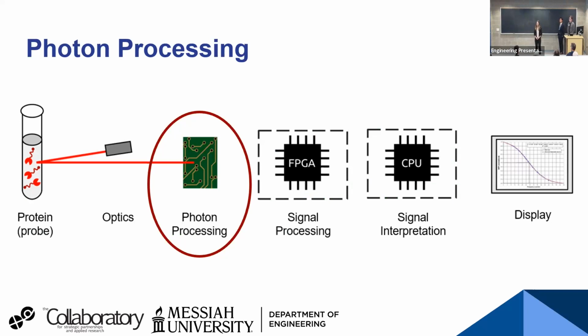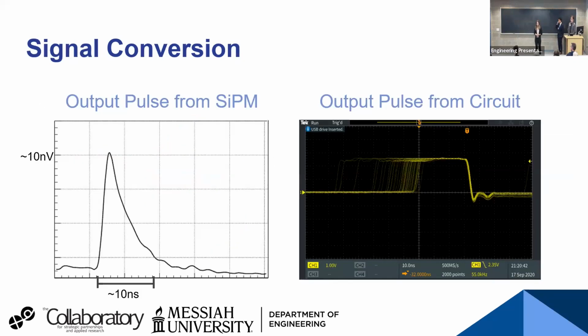So now we'll be looking at what we call the photon processing section of our system. This is the part that takes the light that is emitted by the probe and converts it into an electrical signal for signal processing. To do this, we use a device called a silicon photomultiplier, or a SiPM. The SiPM is a tiny little chip that detects a photon and emits an electrical pulse for it. However, the pulses that come out of the SiPM itself are very small magnitude, around the order of about 10 nanovolts. So in order to actually be able to do some processing on that, we need to convert that to something more like what you see on the right here that is boosted in voltage and is also a digital signal rather than an analog one.